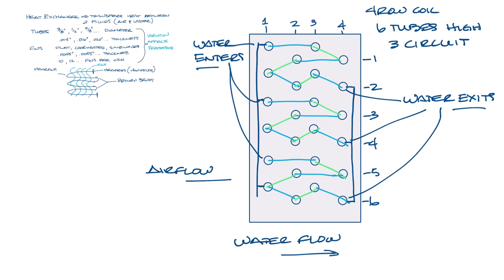If the air flow through this coil is also from left to right, this is a parallel flow coil. If the air flow in this coil is from right to left, then that would be a counter flow coil.